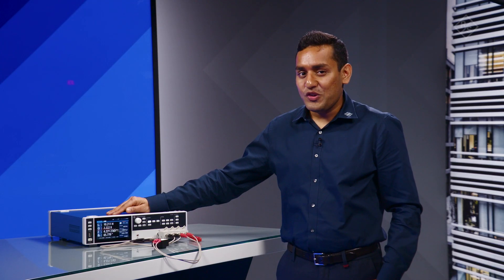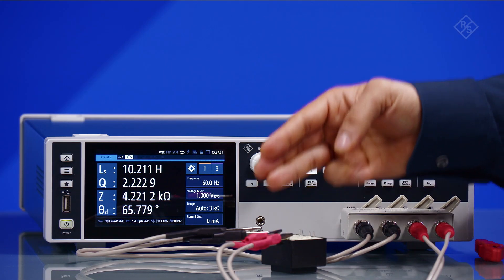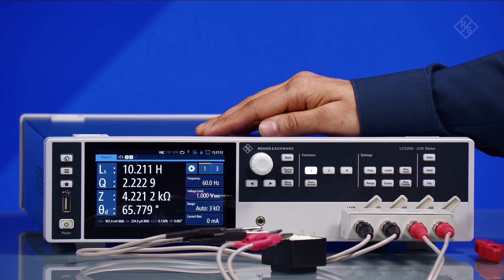Do you now want to measure the secondary inductance of the transformer? Connect the test leads to the secondary winding and leave the primary winding open.